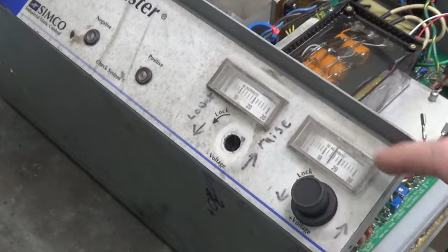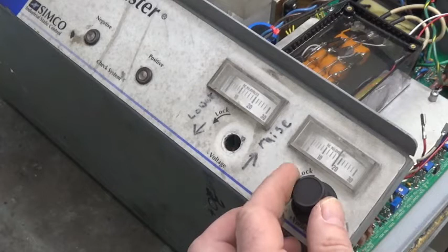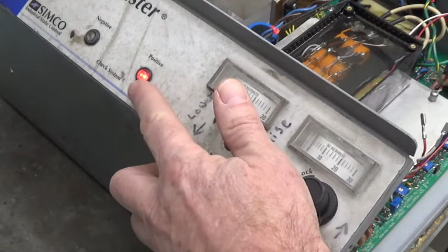There's 15,000 on the meter. There's 20,000 volts on the meter. It's 25. And there's 30,000 volts on the meter, indicating we have 30,000 volts at that output. Let's turn it back down. Okay, we're at 0 again, and our positive check system LED turned on. Now I'm going to install the negative side. We'll test that.